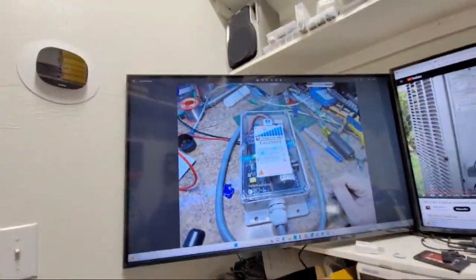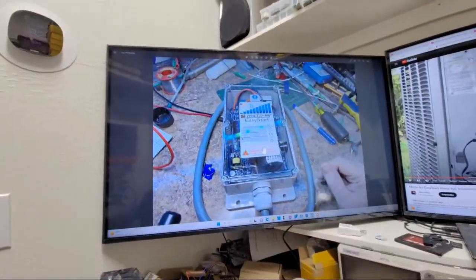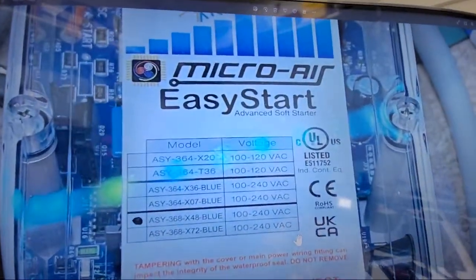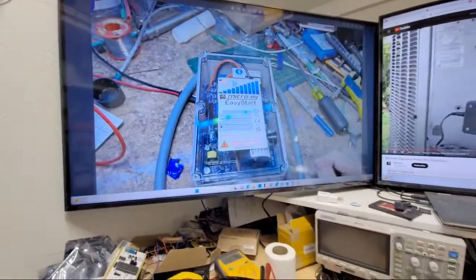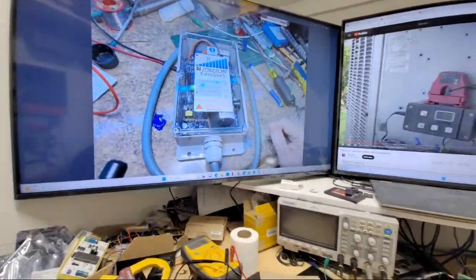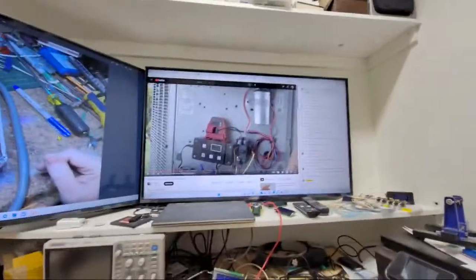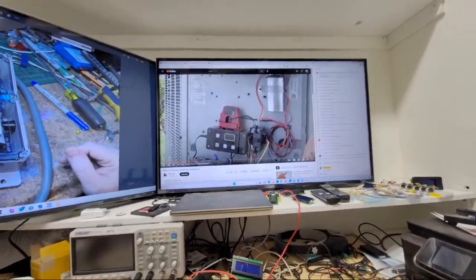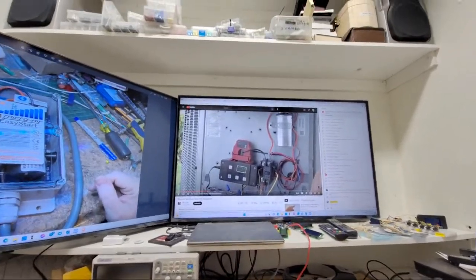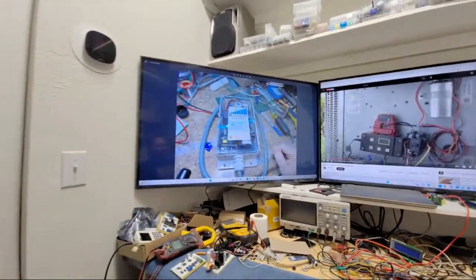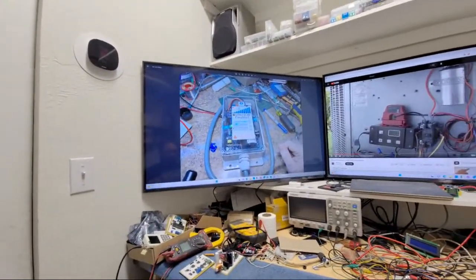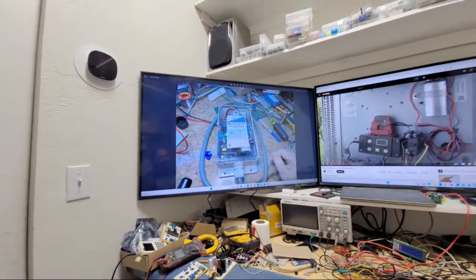I guess I'd better zoom in instead of moving my camera here. But they're calling it a soft start, which is kind of bugging me because I know soft starts are electronic. I'm like, is this just using some relays? Because the guy told me in the video, he says, no, it starts the outdoor fan first, and then after a delay, it starts the compressor. Well, looking at what these are commonly used for, RVs or maybe people with generators, that makes a little bit of sense.